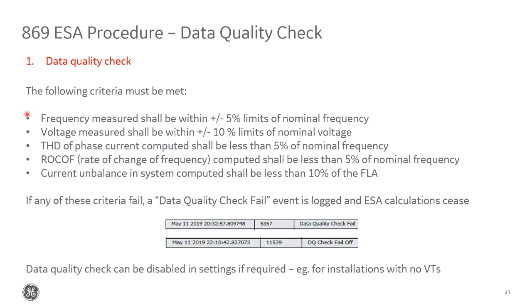If any of these points fails, you'll see a data quality check event logged, and the ESA will be suspended until all of these conditions are normal again and this event clears. So you see data quality check fail, and then after some time, that check fail turned off. With newer firmware versions, we did add a setting where you can choose to disable this data quality check. You might want to do that if the relay doesn't have VTs connected to it, for example. Otherwise, you might constantly have a data quality check failure. But in general, it should be on unless you have some sort of special requirement.